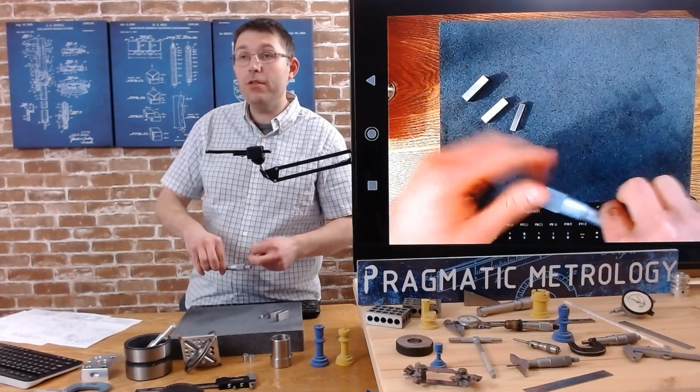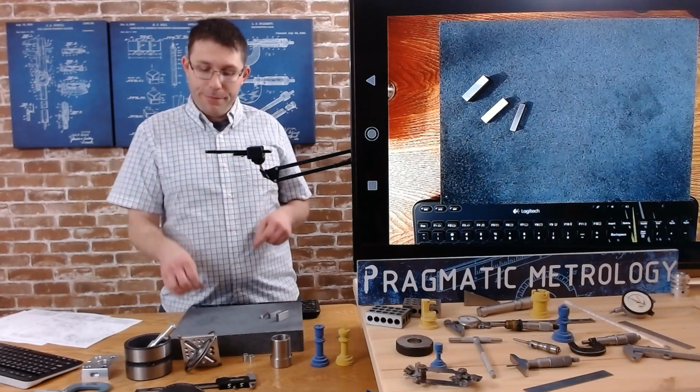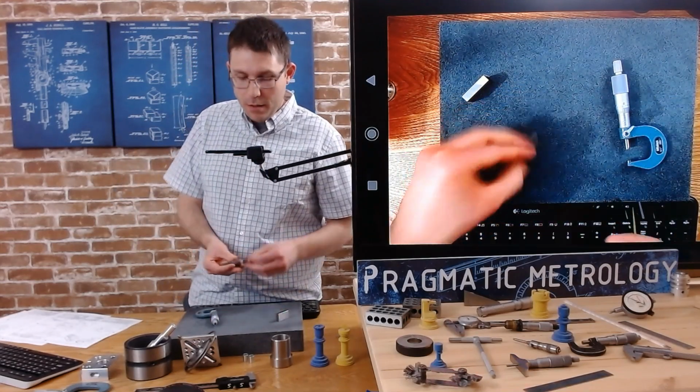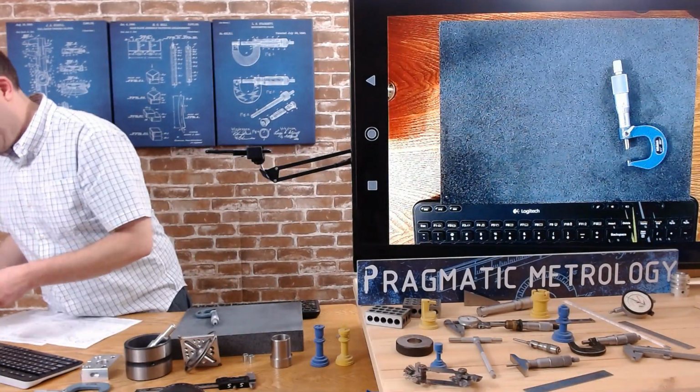Verify as close as you can. If I'm measuring an 875, set up an 875. If you're measuring a 442, set that up. You can use the Jo blocks to build up that stack.